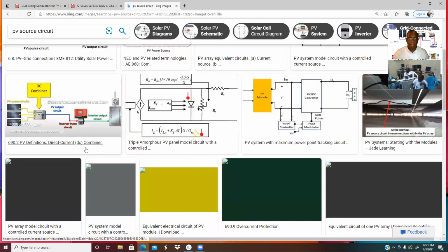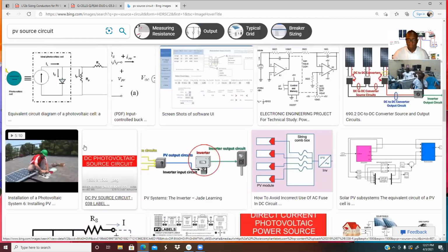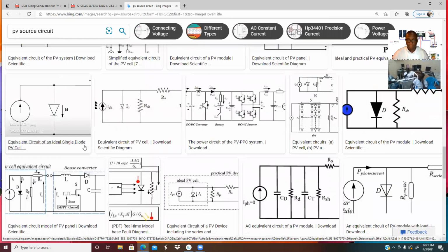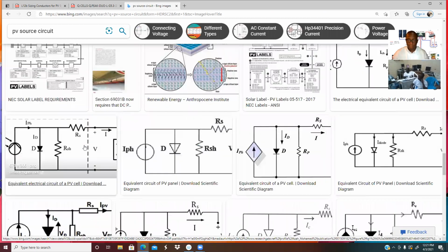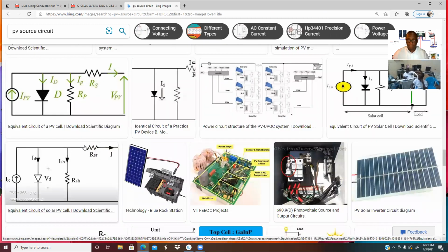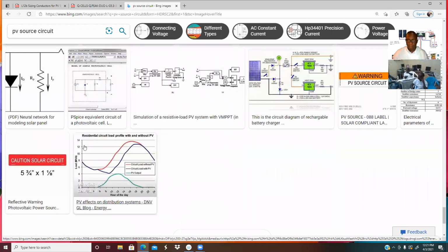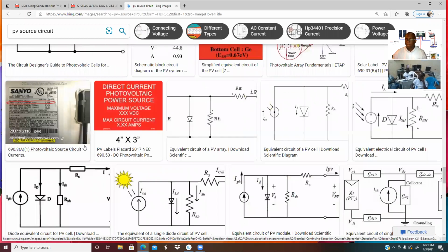So for that irradiance, we multiply by the first 1.25. Then when the system is operating for a complete 3 hours, that is continuous operation, it's ongoing, so anything can happen in that time. If you don't add the additional factor of 1.25, the heaviest rush of current could damage the wire and cause fire, so I will add the additional one.